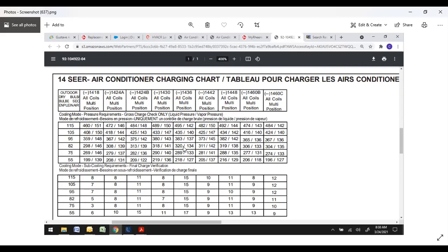We'll come over here. Our gross pressures is 320, 134. Now, rarely will you get exactly that, and don't take that as written in stone. That's just your gross pressures. If you're close to that, you're in the ballpark. At that point, you want to take your 82, come down to 82, come over to your 36 again. So you need 15 degrees subcooling.